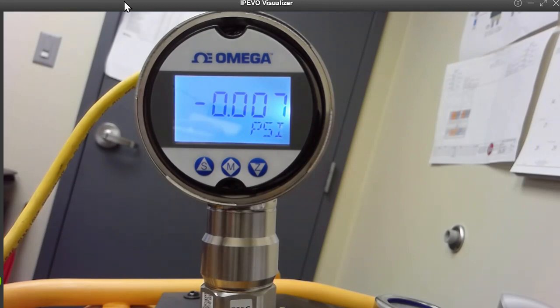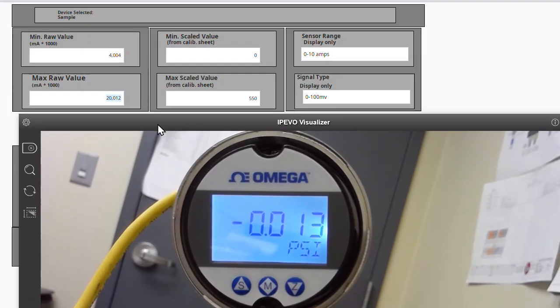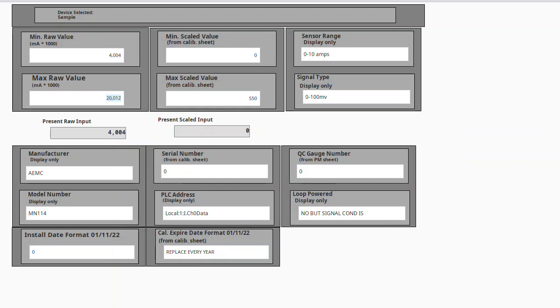We're going to go back to our calibration app, and we'll see that our min value is 0, but we're actually generating right now a 4.003 milliamp signal, bouncing between here. We need to take whatever value is here and put it into the min raw, and that completes the calibration. Make sure you update your calibration application with the expiration date and all of that.